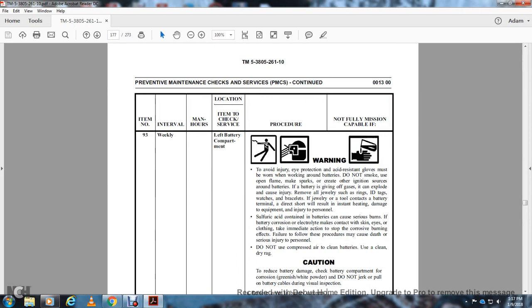Item 93, weekly interval, left battery compartment. To avoid injury, eye protection and acid-resistant gloves must be worn when working around the batteries. Do not smoke or use open flame, and do not make sparks or create other ignition sources around the batteries. If the battery is giving off gas, it can explode and cause injury.